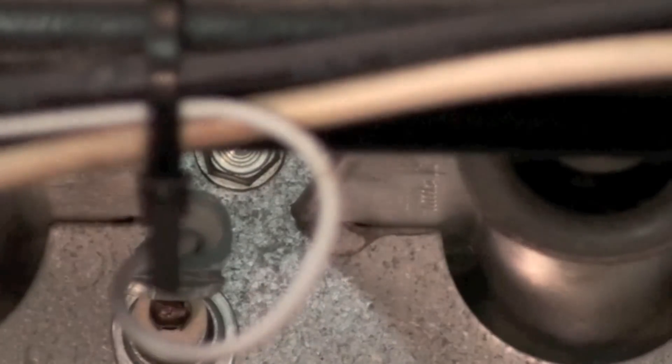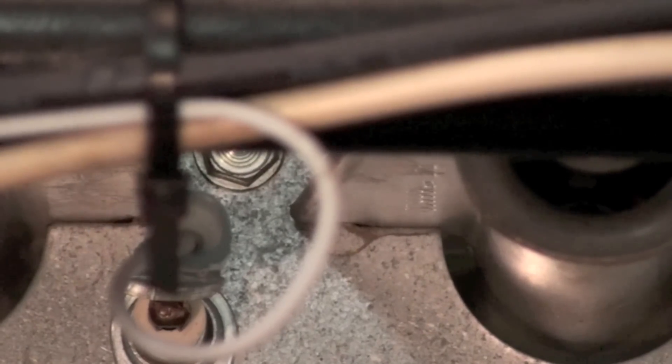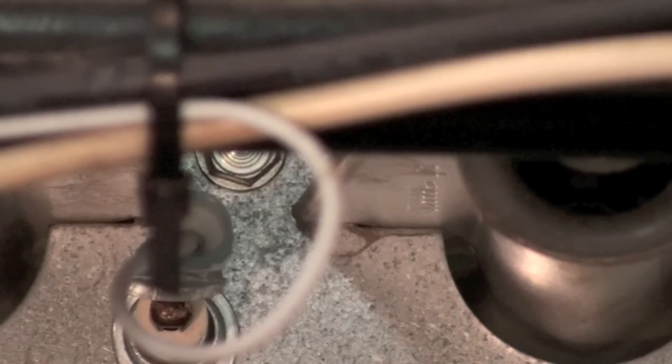Hot surface igniter is over here. This warms up. You should see a yellow glow. Then you see the blue flame come across and then it shuts off again. These things can do this intermittently. They can do it every time. If they do it every time, they usually try three times and they shut down, wait for an hour, and then try again. So if this is the kind of short cycle you have, it's probably not sensing flame.